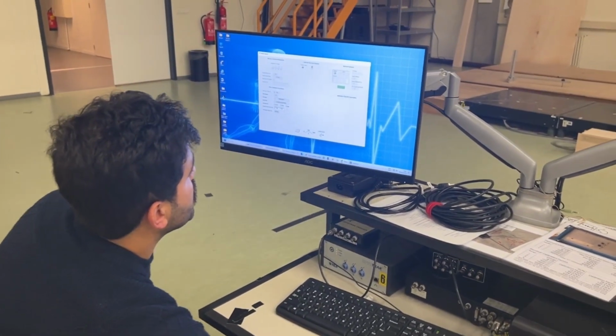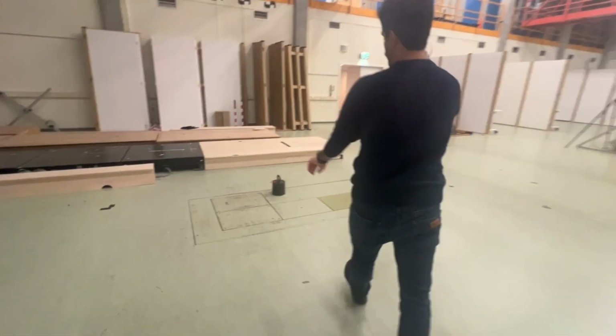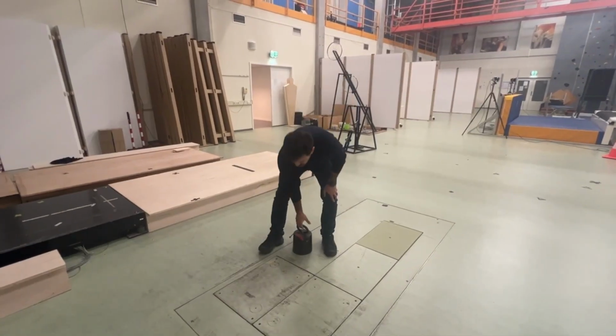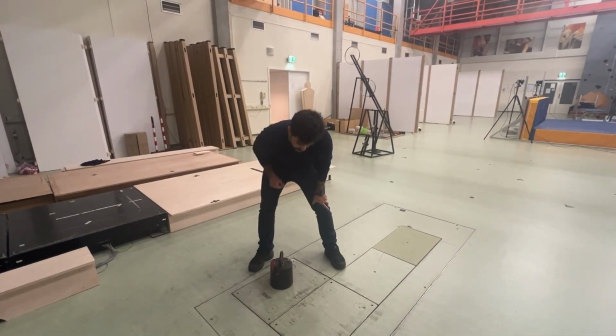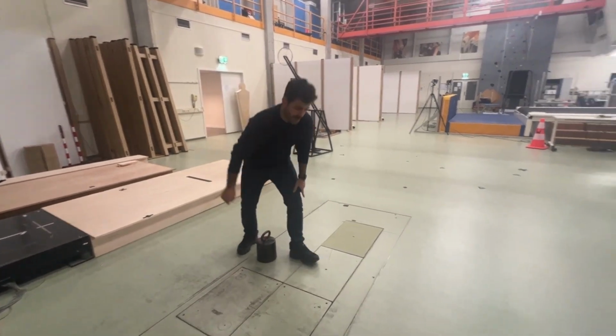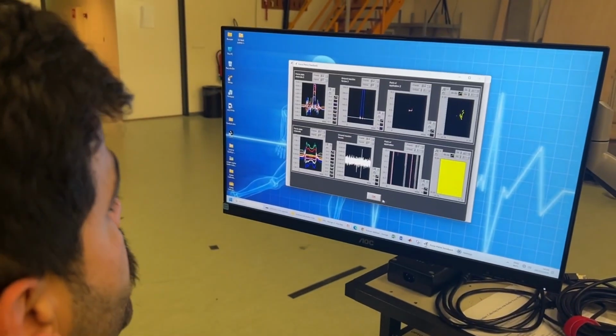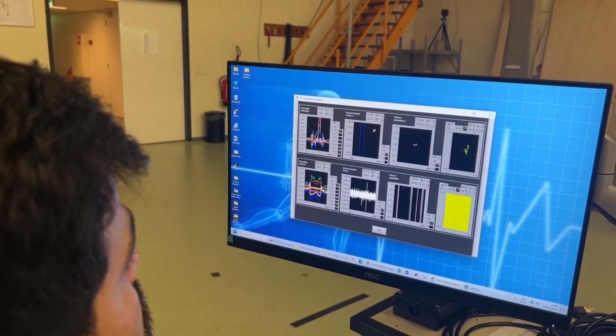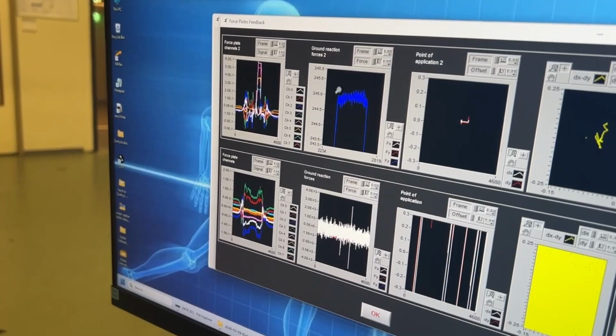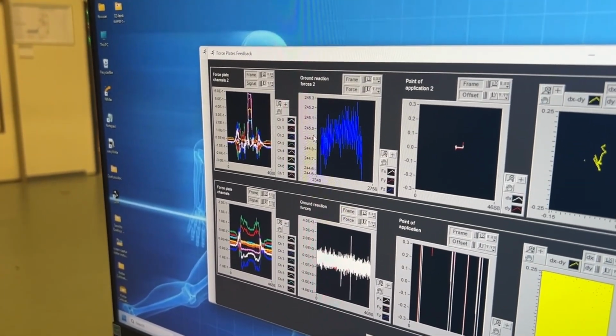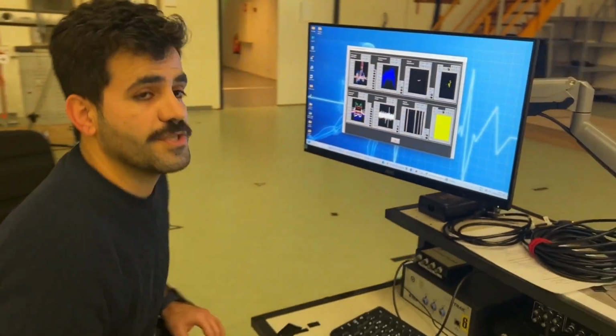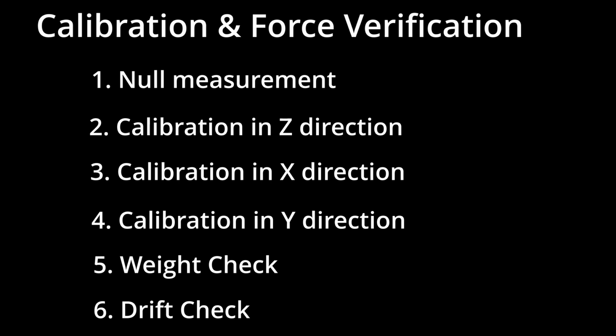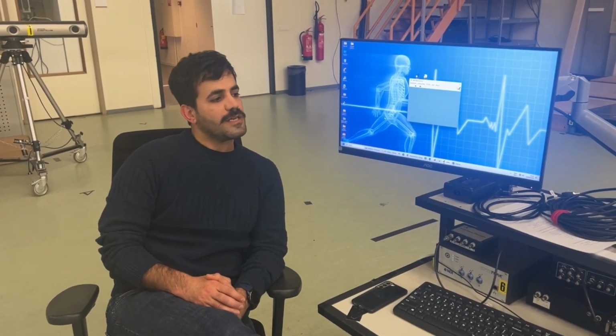I start data collection. I put the 25 kilograms on the force plate. Get out. Let's check the data. I stop the data collection, and let's zoom in the data. As you can see, the data is around 245 Newton. So our calibration went well. Last thing to check is the force plate drift. If the amplifier are warm up properly, the drift should be less than 3 Newtons in 100 seconds.